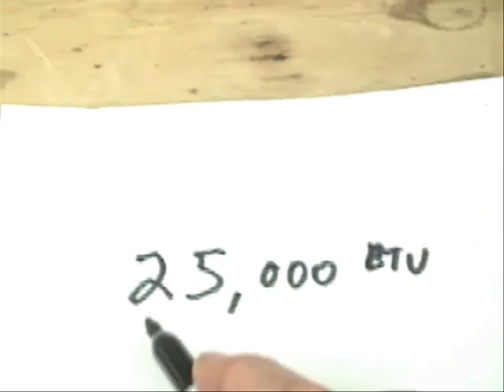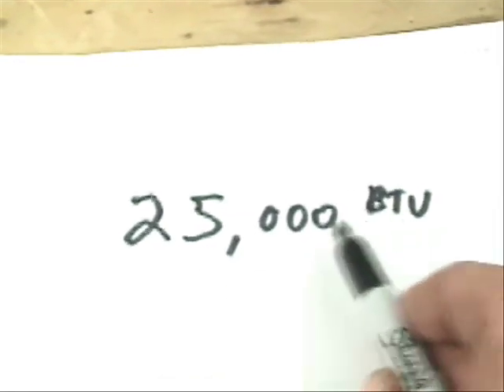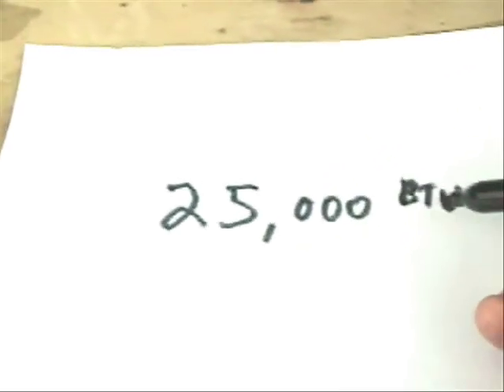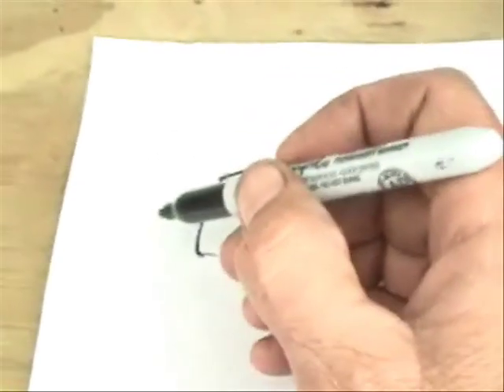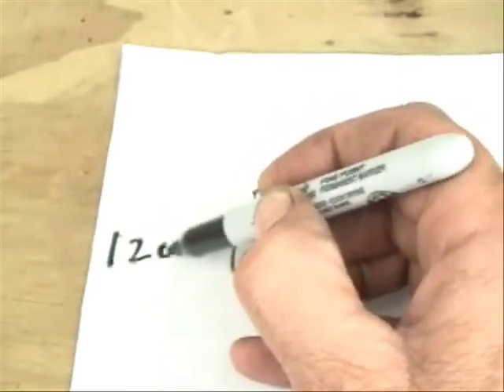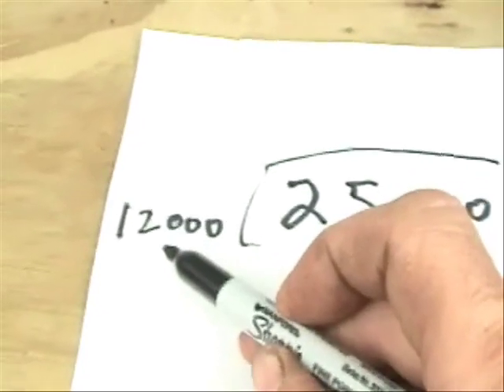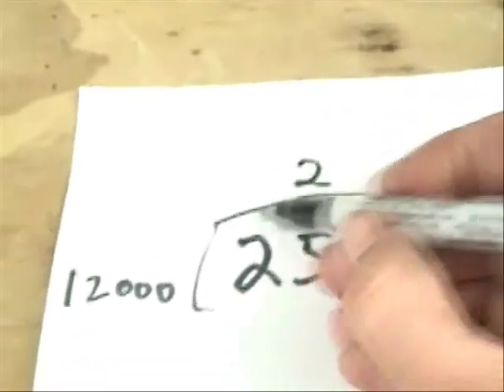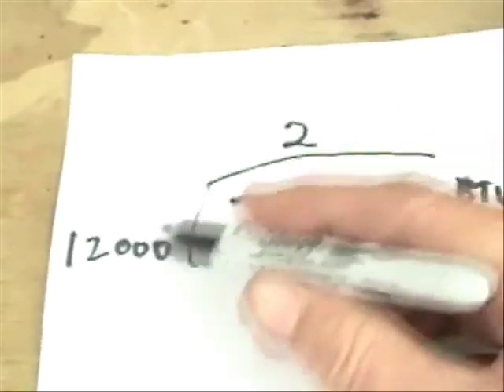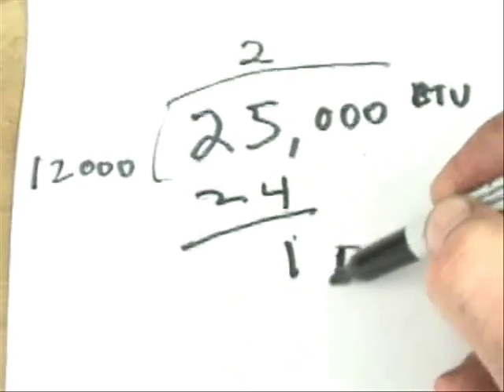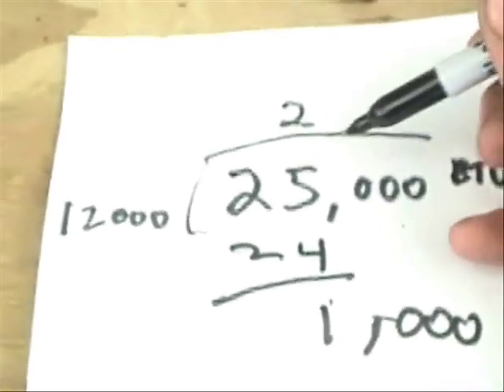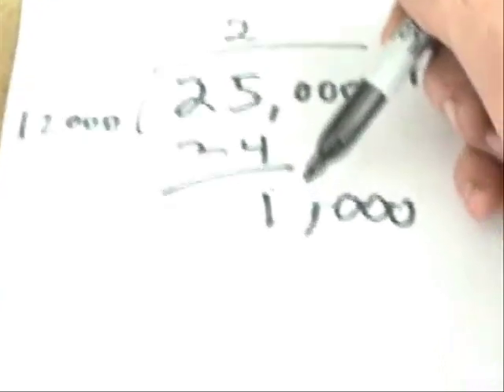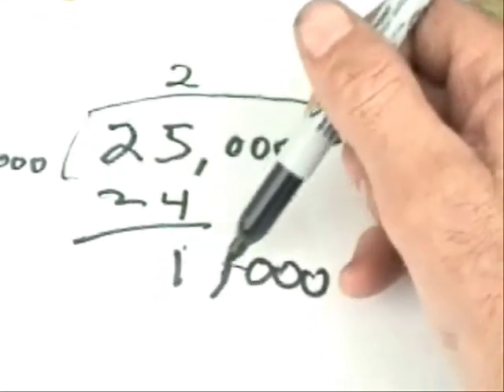If we have an air conditioning system that is rated at 25,000 BTUs, to calculate exactly how many tons this is equal to, we divide it by 12,000, because there are 12,000 BTUs in a ton. That's going to be 2 tons, but also there's an extra 1,000 BTUs. So what we have here is a 2-ton air conditioning system, which is actually slightly over — it's an extra 1,000 BTUs.